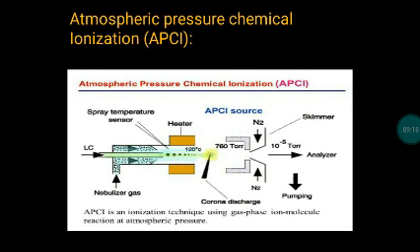Coming to the next technique: APCI, or atmospheric pressure chemical ionization. APCI is an ionization technique using gas-phase ion-molecule reactions at atmospheric pressure. It is a type of soft ionization technique and is a combination of chemical ionization and electrospray ionization with some deviation. For the working part: sample is injected into the capillary, and this capillary is heated by a heating coil.